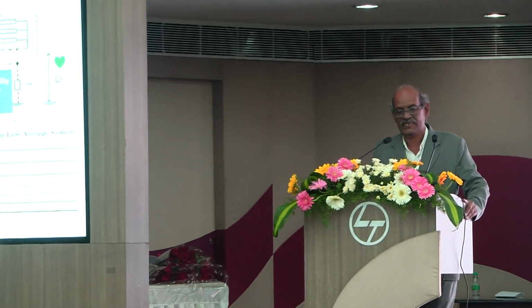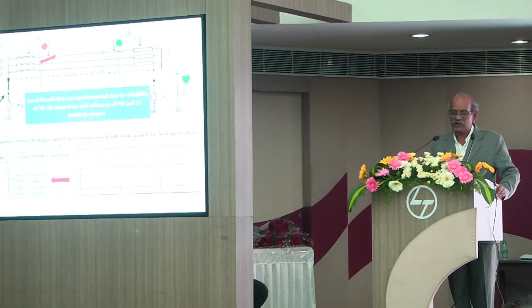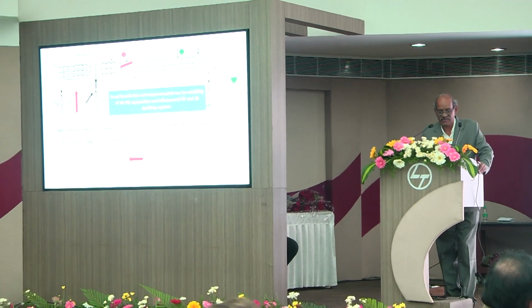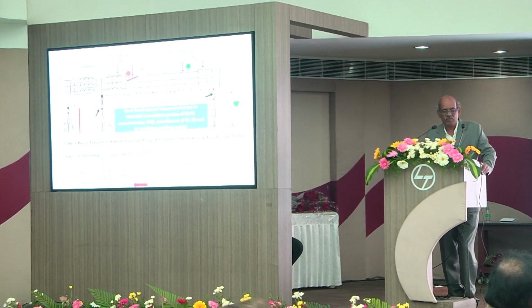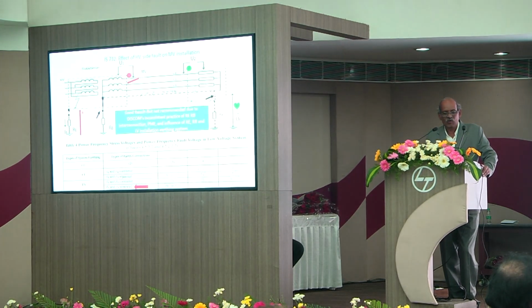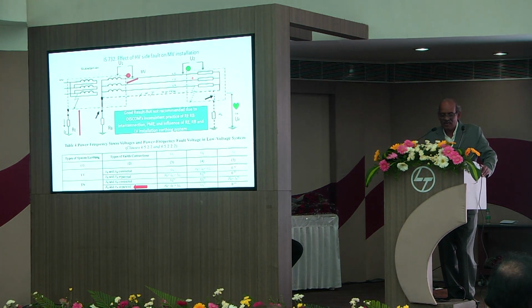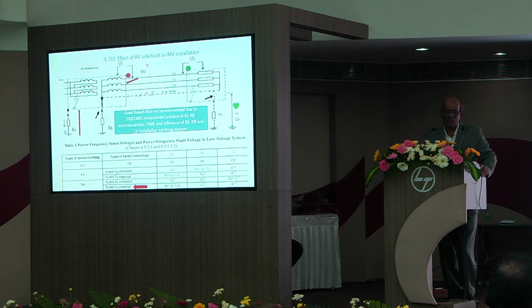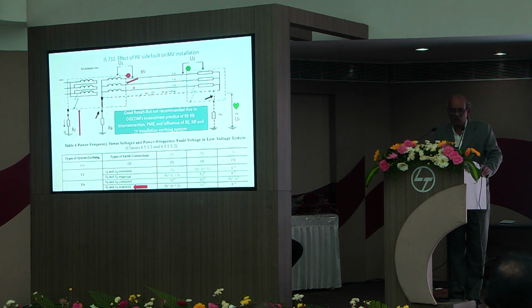And see, suppose there is no interconnection between the body and the neutral. In the absence of interconnection, the voltage will be impressed more at the transformer LT. The LT winding will be impressed with more voltage, and you will be safe. The person as well as the equipment will be safe. In another situation, this is open and both are safe, but the transformer will be impressed with a high voltage.